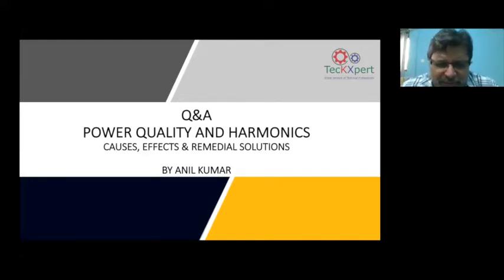See, now putting at individual level a passive broadband filter is expensive. I will never recommend that. Putting passive filter all across at the drive input is an expensive choice. The best solution is to put line reactors at the VFD inputs. Sometimes the VFD comes with a DC choke. Sometimes the VFD comes with the input line reactor. An input line reactor of 3% can bring down the harmonics to the tune of around 30%. And here, the right approach is to analyze the problem at site.